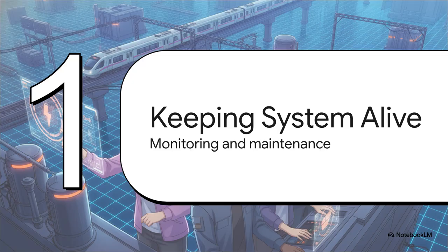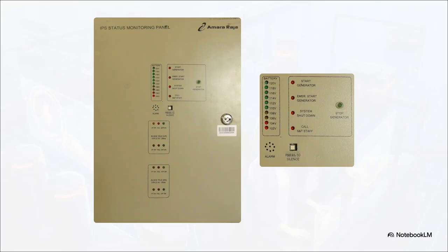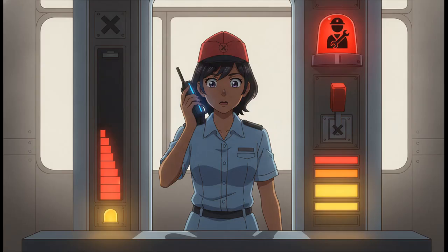Finally, let's wrap up with Section 5, keeping the system alive. Think of the IPS status monitoring panel as the IPS dashboard. This panel is wall-mounted right inside the station master's room. It basically allows the human operators to see exactly what that hidden power rack is doing at a single glance, relying on a simple LED bar graph and some very critical audio-visual alarms. And these alarms are designed in escalating thresholds to stop a disaster before it starts.